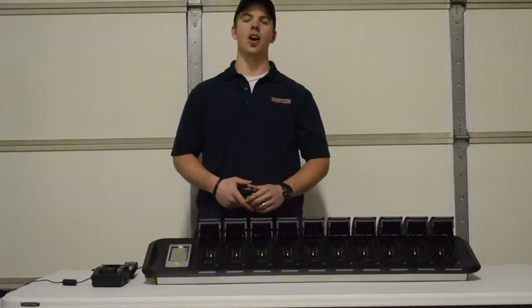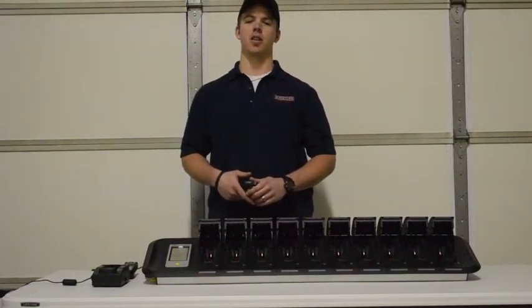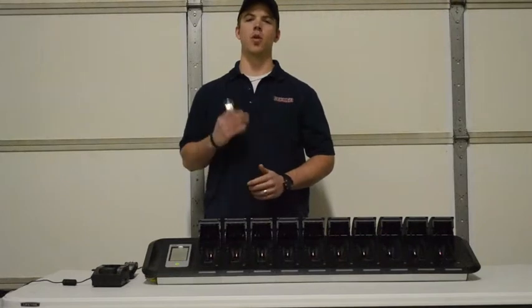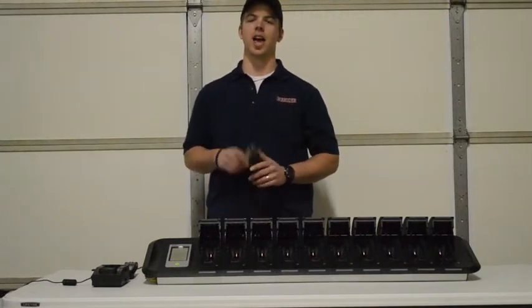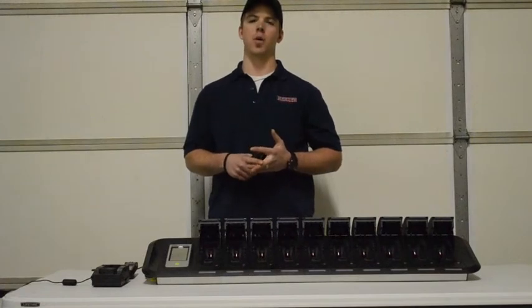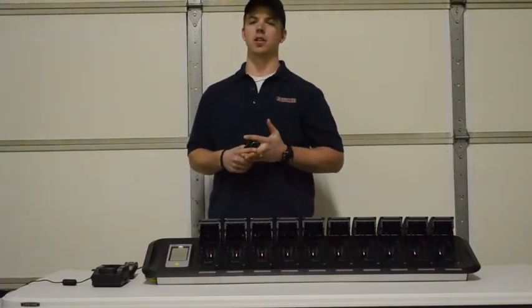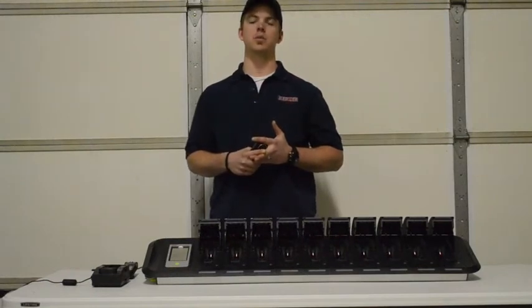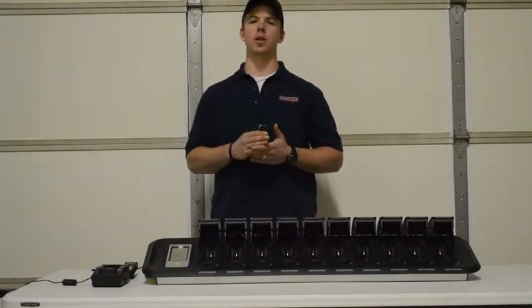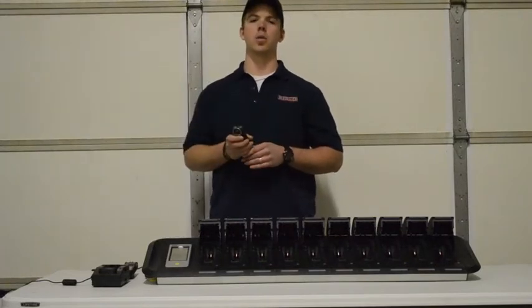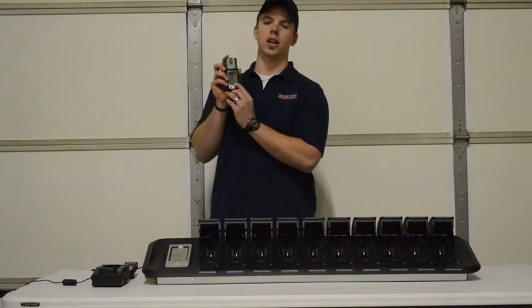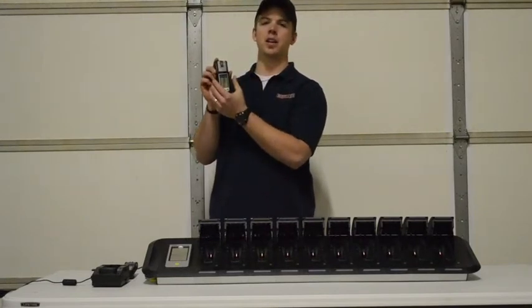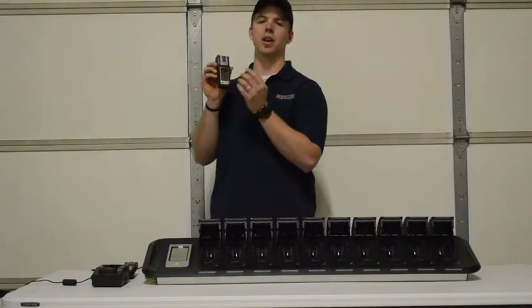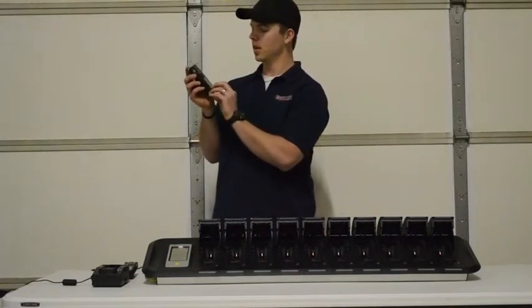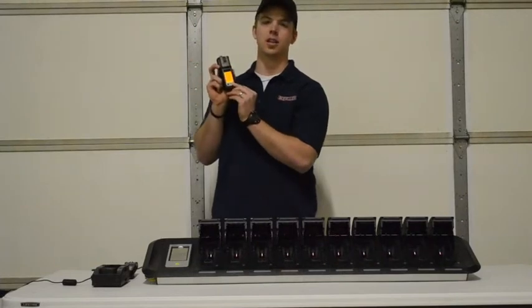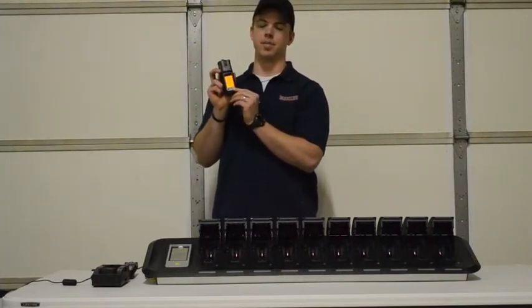Now I'm going to be going over the alarms for the Draeger X-am 2500 gas monitor. There's many different types of alarms, but there's 4 main ones that you need to be concerned about. The A1 alarm is your lower alarm point. For example, a CO sensor is set at 35 parts per million for the A1 alarm. Once your monitor reads 35 or higher, the A1 will go into alarm. On your monitor, it will say A1, start vibrating, the LED will start flashing, and there will be a noise of an alarm. To acknowledge the alarm, press OK. You can only acknowledge an A1 alarm.